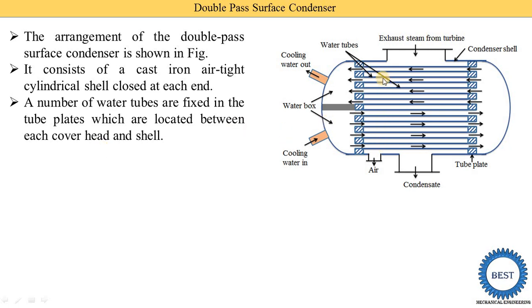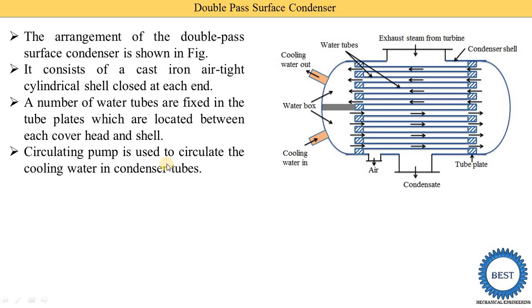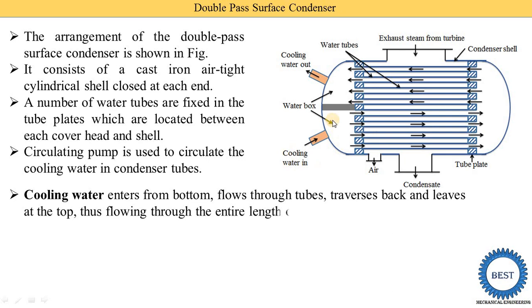A circulating pump is used to circulate the cooling water through the condenser tubes. Cooling water enters from the bottom, flows through the tubes, travels back, and leaves at the top — thus flowing through the entire length of the condenser twice. This is one round, and this is the second round. That is why it is called the double pass surface condenser.